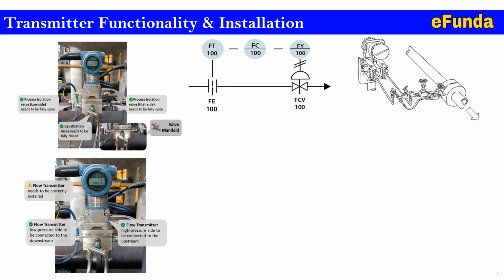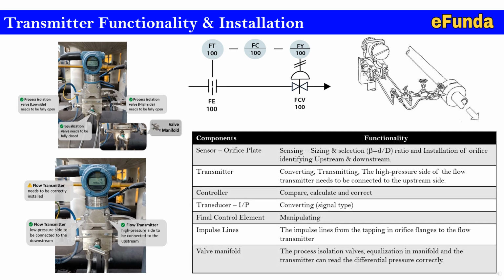Now we will see the components and their functionality. One can refer to the chart where the sensor here is the orifice plate. Orifice plate functionality is sensing, that is sizing and selection, where the beta ratio is equal to small d by capital D ratio, and installation of an orifice involves identifying the upstream and downstream location, that means the flow direction will be marked on the line. Transmitter converting or transmitting: the high pressure side of the flow transmitter needs to be connected to the upstream side so as to have the differential pressure across the orifice measured by the flow transmitter, that is a DP type flow transmitter.